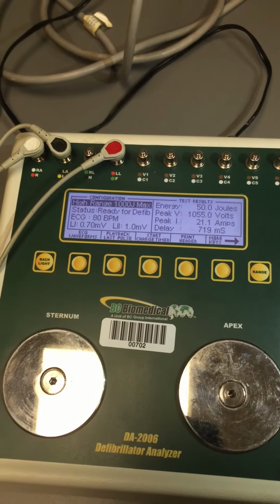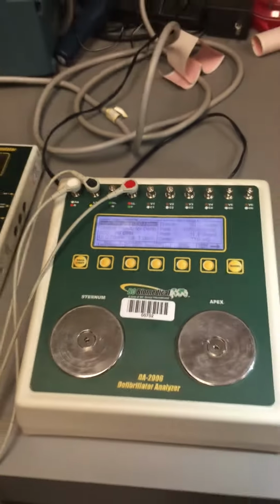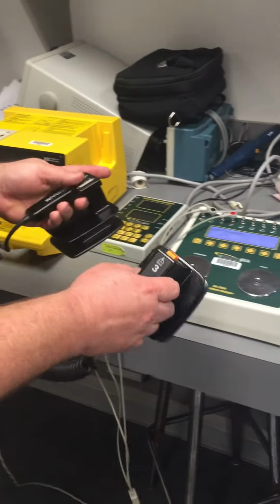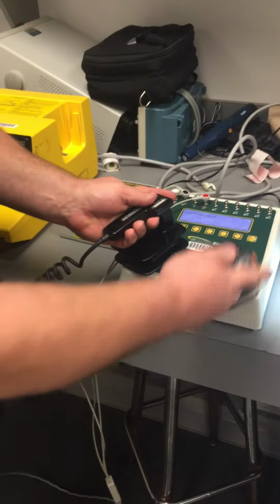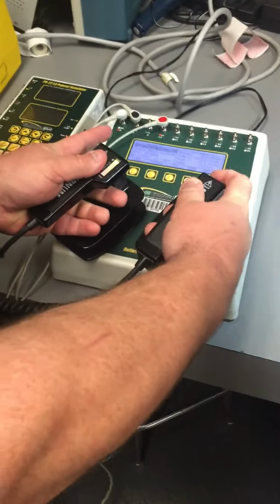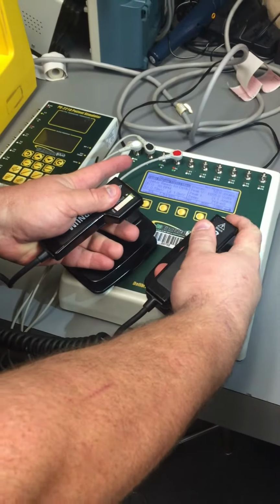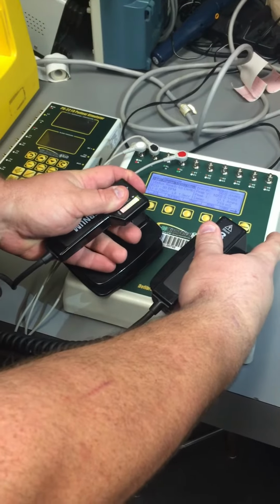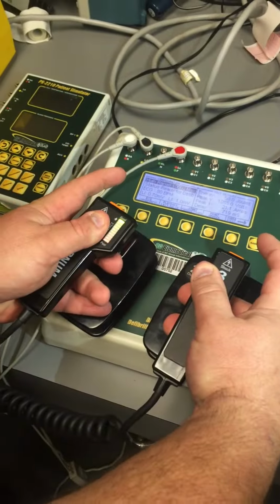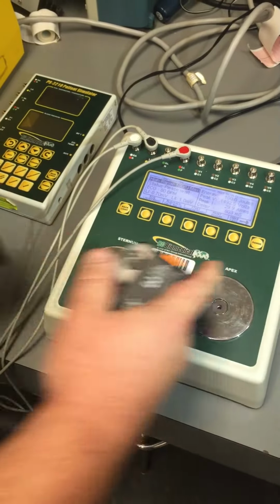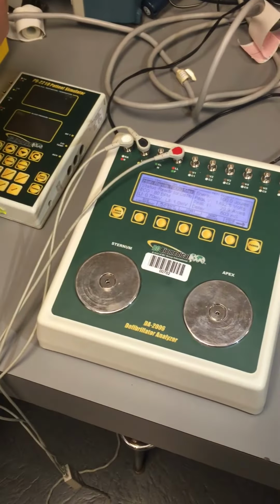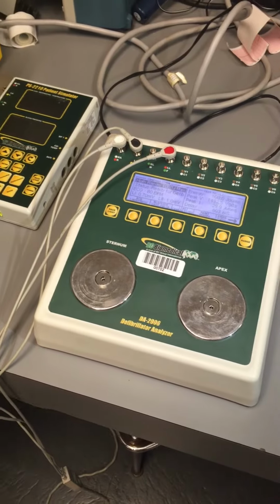So that's very important. I'm going to go to 100. I'm going to show you another test. I'm going to charge this. I'm going to press just one button. The device should not discharge. I'm going to press just the other button. The device should not discharge. I'm actually going to press both buttons and it should discharge. And notice the energy there was at 100 joules.